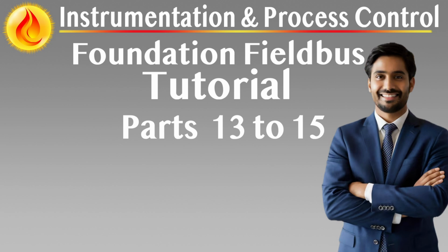Trunk and spur cabling must be installed with care. The trunk, which carries both power and communication signals, runs from the control room or marshalling panel to junction boxes in the field. Spurs connect individual devices to the trunk. Installation must observe strict maximum lengths, typically 1900 meters for the trunk and up to 120 meters cumulative spur length depending on device count. Cable trays and conduits must avoid running parallel to power cables, and minimum separation distances must be maintained to reduce EMI exposure.